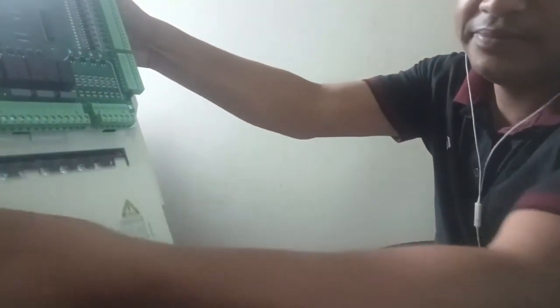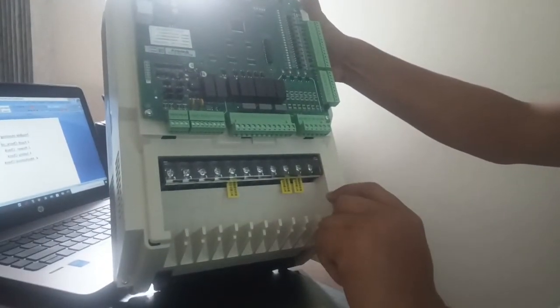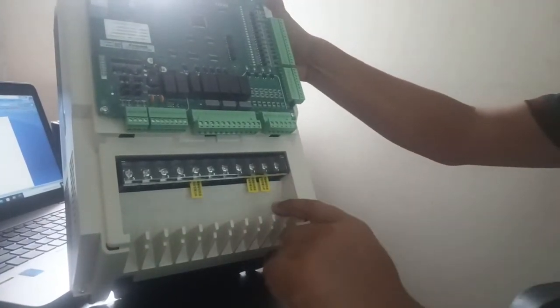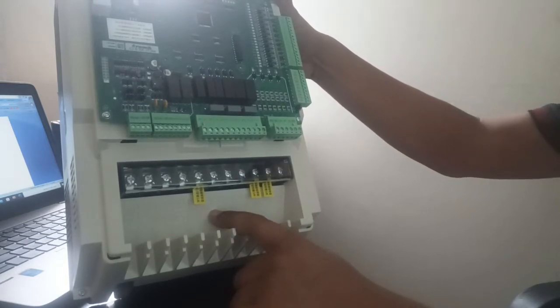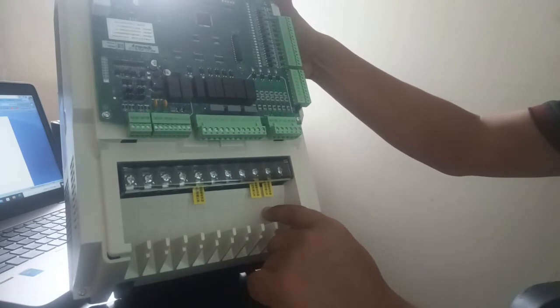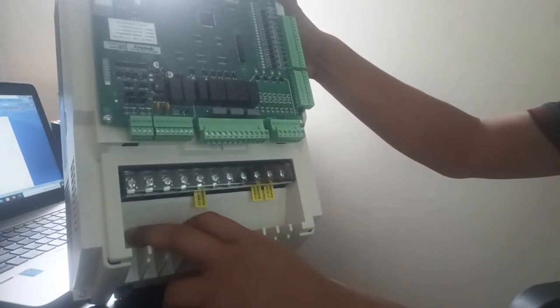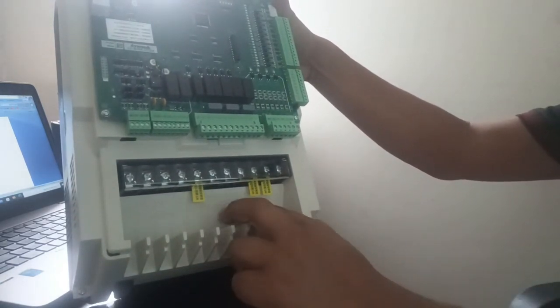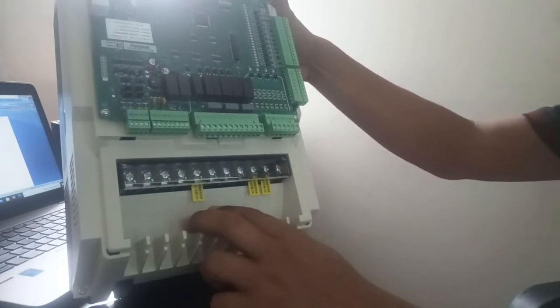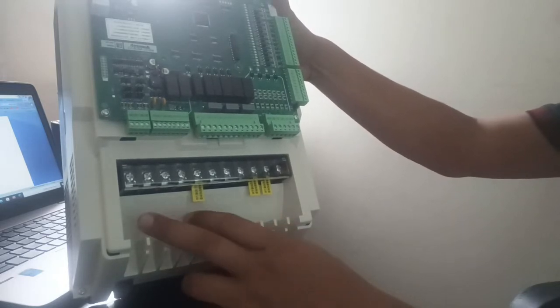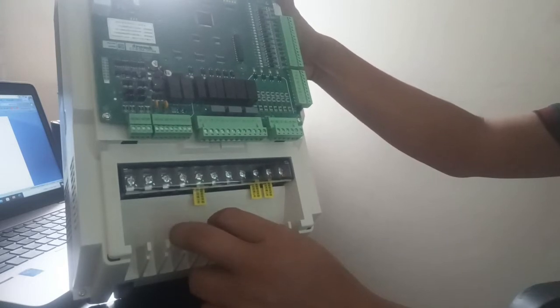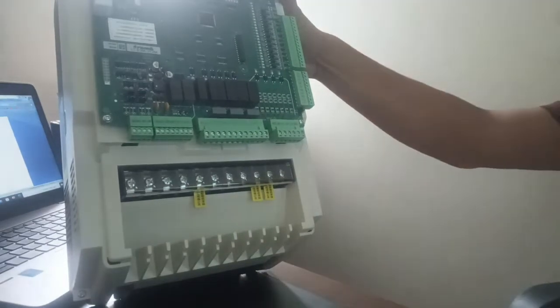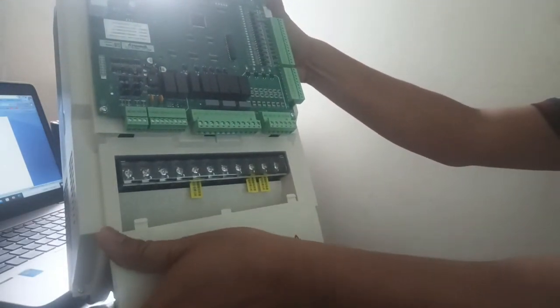Number 2, we'll check the power supply. Where is the power supply? Here. R, S, T is 3-phase, P and B plus is for the braking resistor, U, V, W is for the motor, and that's for earthing. Between phases R and S, S and T, R and T, it should be available from 380 to 400 volts. You can check from earthing, it will be 220 to 240. My reminder: for phase, neutral, and earthing, it must be below 1.